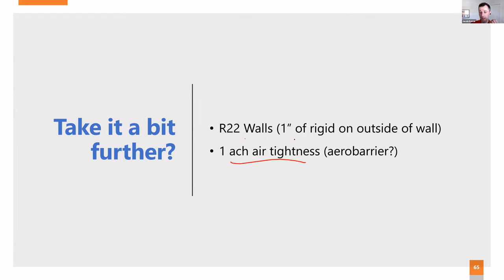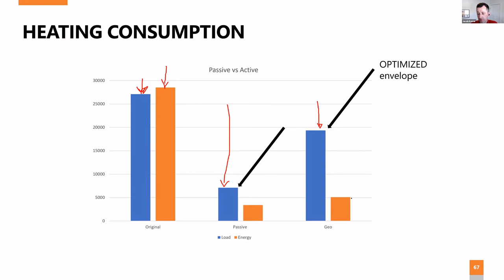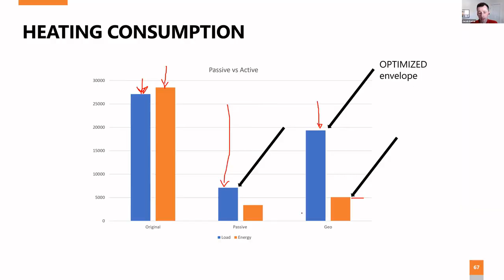With a furnace, because it's less than 100% efficient, your energy consumption is higher than your heating demand. With a passive approach, you reduce the heating demand, and the mechanical system becomes an afterthought. With a geo system, you still optimize the envelope, do the easy things like windows and a bit of envelope, past the point of diminishing returns, and then use the efficiency of geo to divide that load by 4, getting you to almost the exact same spot.